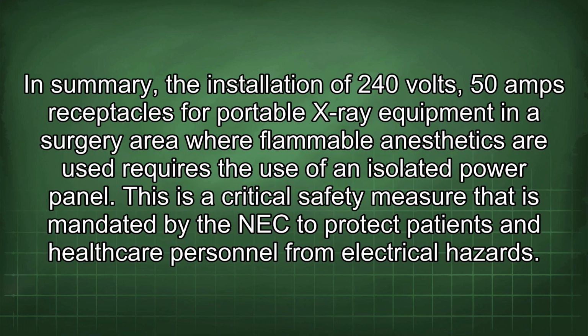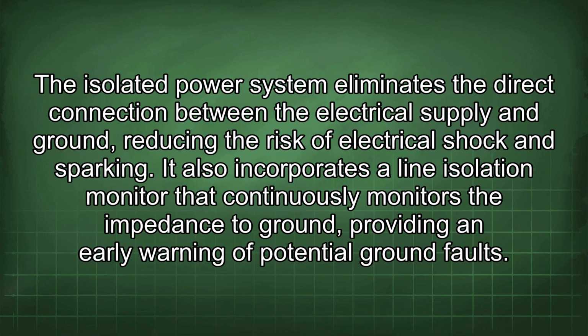In summary, the installation of 240 volts, 50 amps receptacles for portable X-ray equipment in a surgery area where flammable anesthetics are used requires the use of an isolated power panel. This is a critical safety measure that is mandated by the NEC to protect patients and healthcare personnel from electrical hazards. The isolated power system eliminates the direct connection between the electrical supply and ground, reducing the risk of electrical shock and sparking. It also incorporates a line isolation monitor that continuously monitors the impedance to ground, providing an early warning of potential ground faults.